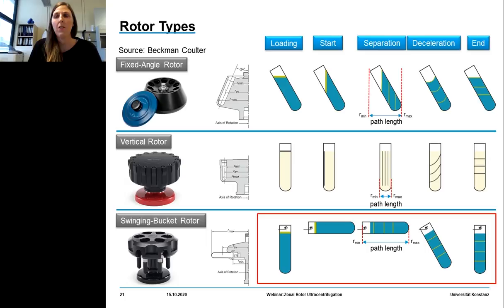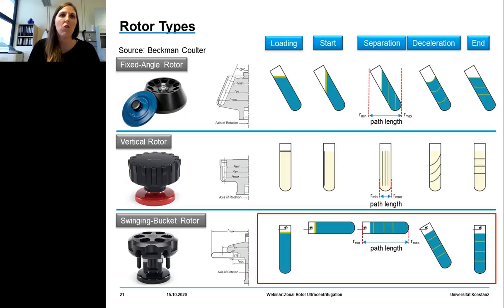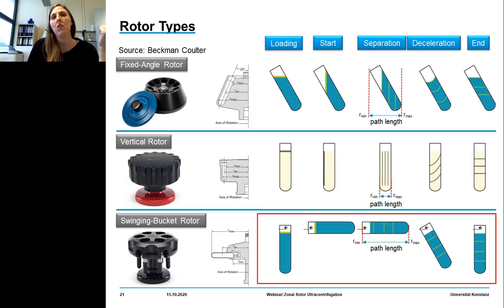Now we have the density gradient with the sample on top — what about the rotor? There are several different rotors available: the fixed angle rotor, the vertical rotor, and the swinging bucket rotor. The selection depends on sample volume, number of sample particles to be separated, particle size and/or density, desired runtime, and desired quality of separation.